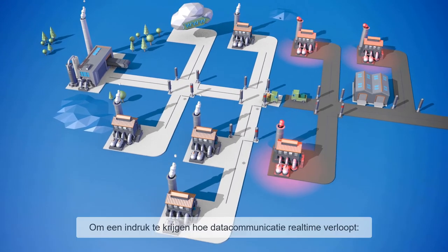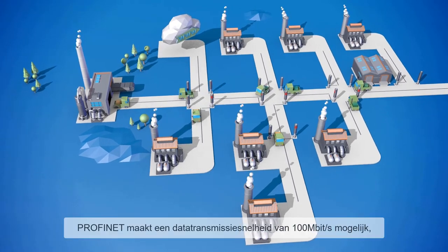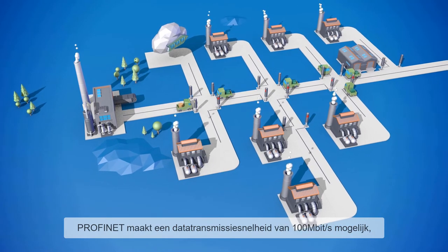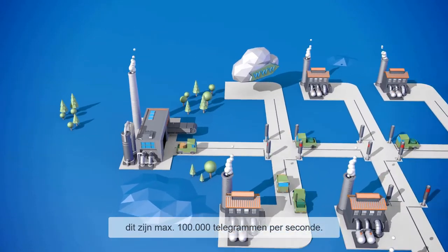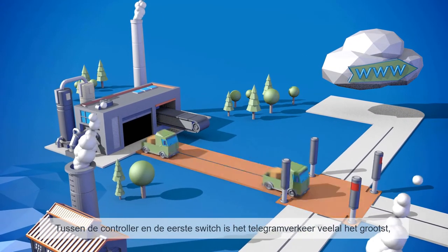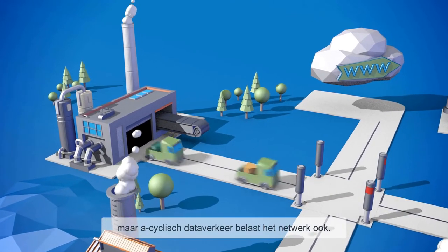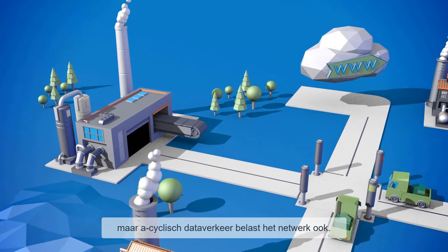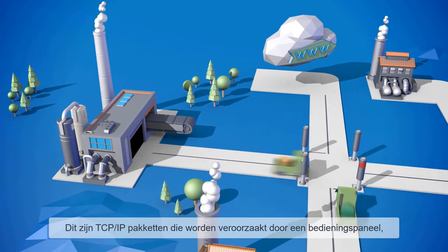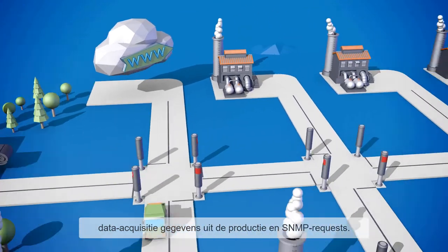Here is an example of data communication in real time. The PROFINET technology enables a data transmission rate of 100 megabits per second, meaning a transfer of up to 100,000 telegrams per second. The telegram traffic is often greatest between the controller and the first switch. However, acyclic data traffic also creates a load on the network, including data packages from TCP/IP traffic caused by a touch panel, data from production data acquisition, or even SNMP requests.